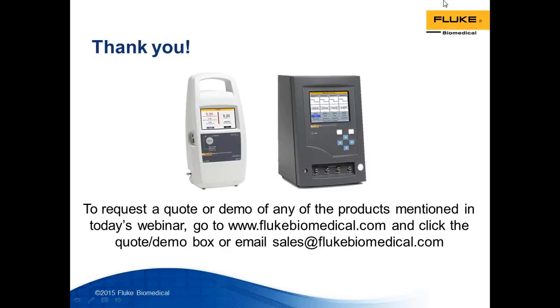So that's one. Number two, it has automatic testing built into the unit, which the IDA4 did not have. So we walked through the template side where you can see that you can prescribe what to test, and that's in the product. You don't really need any software to do that. You could just do it on the IDA5 standalone. Number three, it has plug and play. So we've gone away from custom accessories completely, where with the IDA4 you had to buy a specific keyboard, a specific scanner, a specific printer. You don't have to do that anymore. You can use any USB compatible barcode scanner or keyboard, and any PCL5 or above printer. So those are some of the advantages over the IDA4.